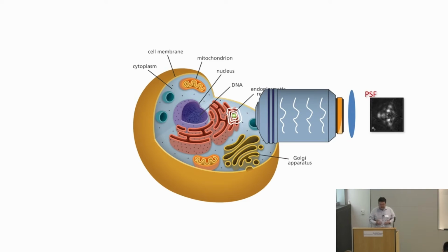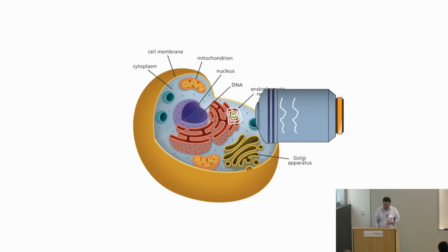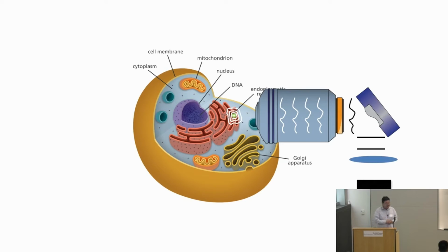On top of that, it's just very difficult to pinpoint the center of this molecule. For example, look at this very aberrated PSF. Adaptive optics works by putting an adaptive element into the pupil plane of the objective, and therefore you can curve the reflective membrane surface exactly to the wavefront shape, and therefore correct the wavefront. And still, if you put a tube lens over here, you will get a fairly nice diffraction-limited point-spread function.